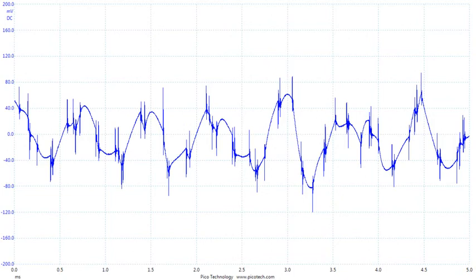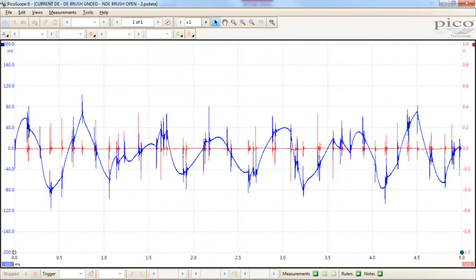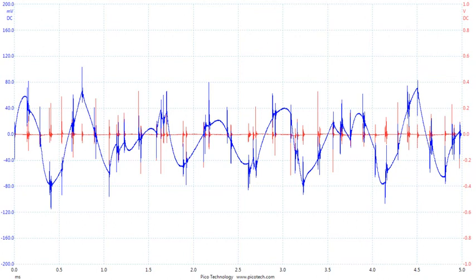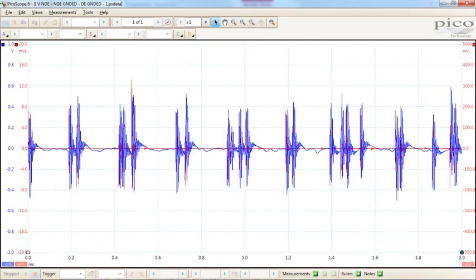It's the same one. This is current with the drive end brush grounded and the non-drive end brush open, and that's the current on the drive end as well. You can see the same thing where you get breakdown. See the influence there, and it's very similar to your breakdown pulses. Again, this is now 0.4 amps, and that's volts.